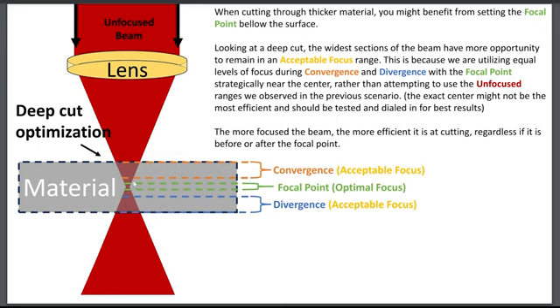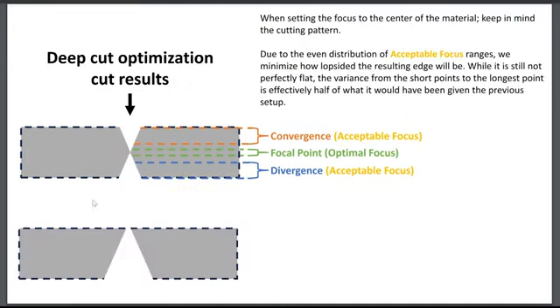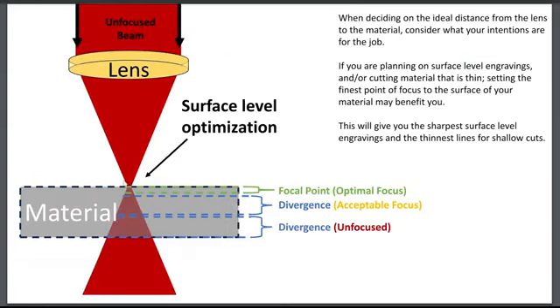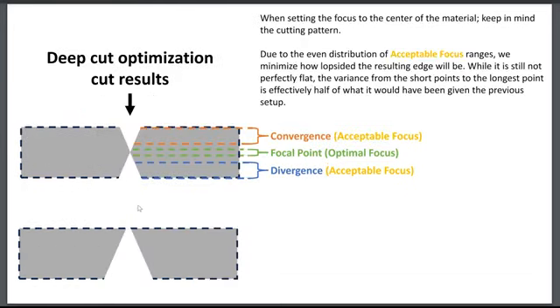So definitely do some tests. A lot of the research I've found and some of my own tests confirm that this will give you an efficiency gain when it comes to cutting through thicker material, but your mileage may vary. Another benefit of setting it up this way is if you're looking at the surface level optimization, right? If the beam is powerful enough to cut all the way through, because of that hourglass shape, which is something you can't get away from, you have a big slant in your cut.